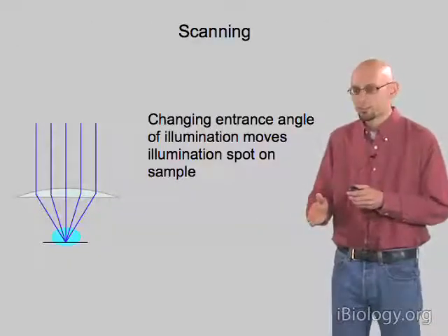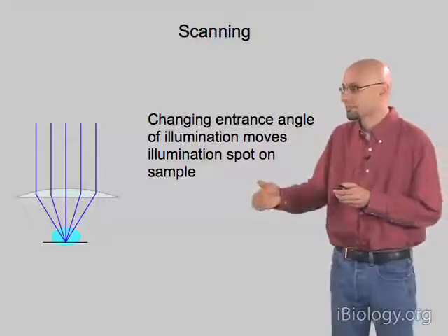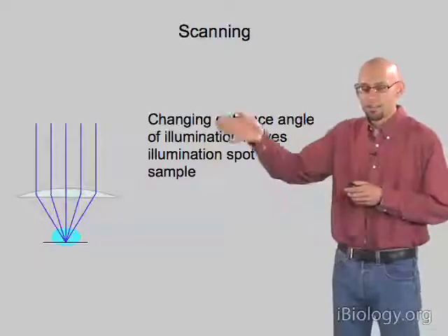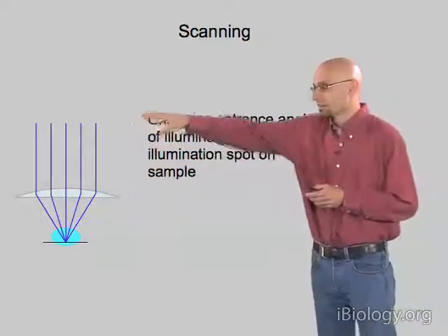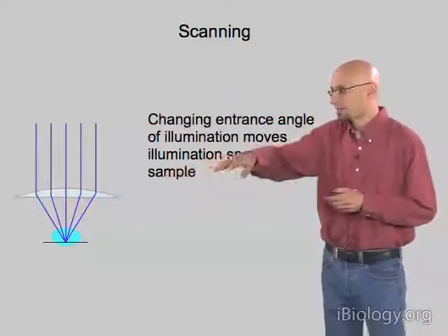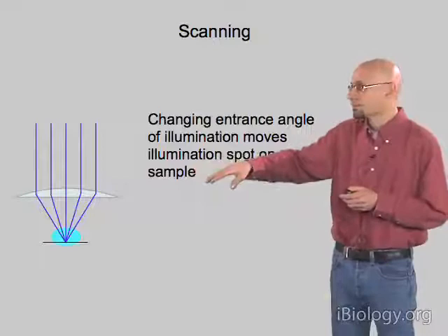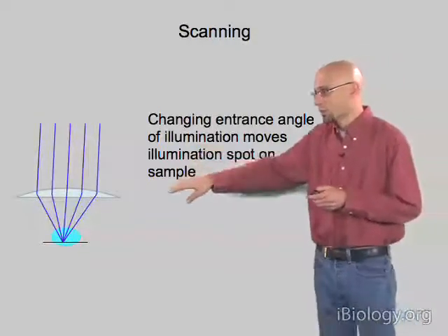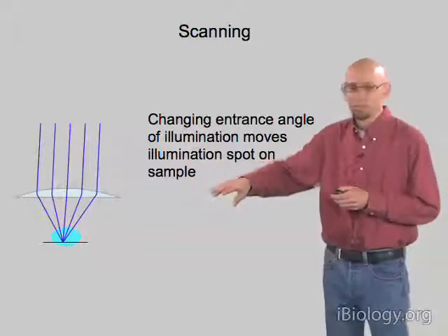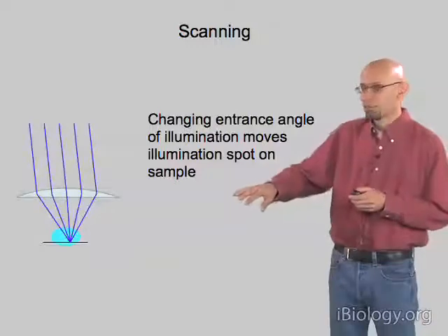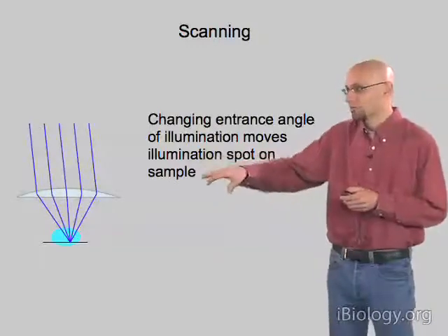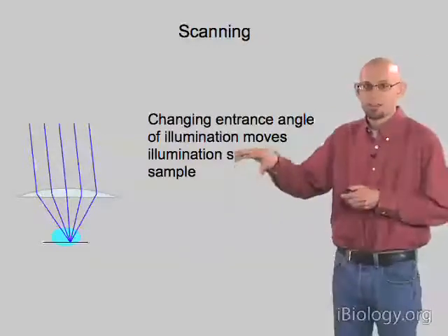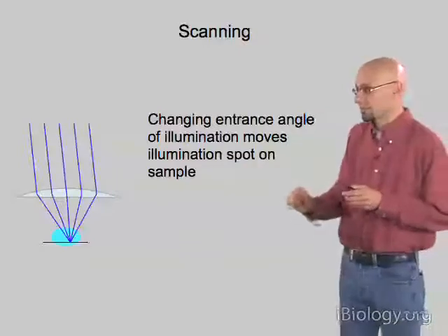It doesn't do us any good to just image a single spot in our sample — we want to have a grid of spots. To do that, we can change the angle of illumination as it enters the objective. If we come in with light perpendicular to the plane of the objective, it comes to a focus exactly in the center of the field of view. If we tilt that beam so it's coming at an angle, we move the focal spot off-axis, and so we can record from the left or right side of the sample. By changing the angle of illumination, we can move the illumination spot across the sample.